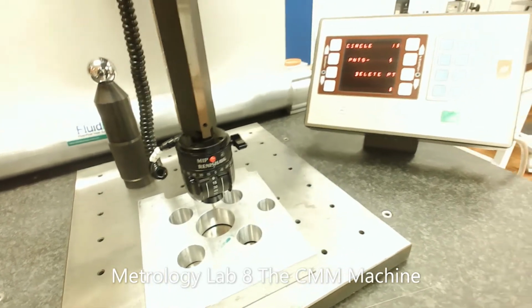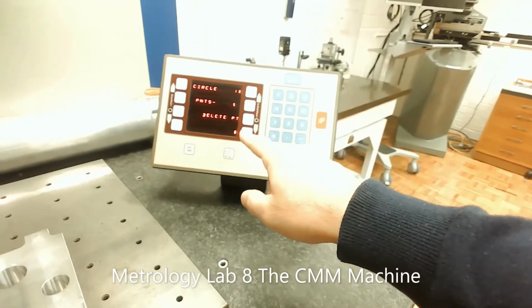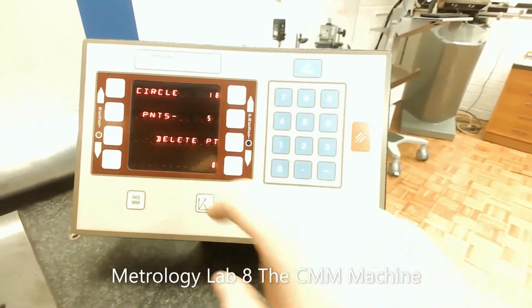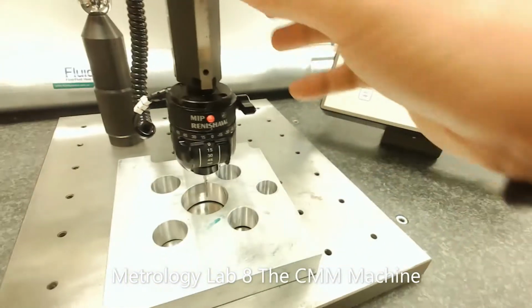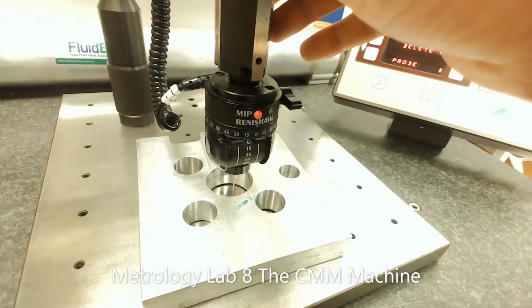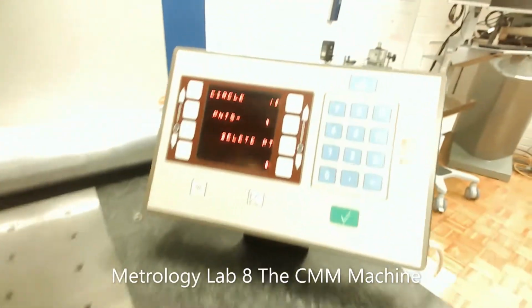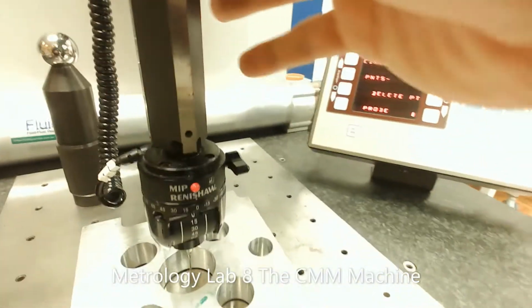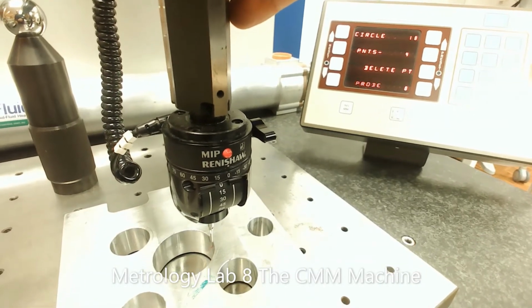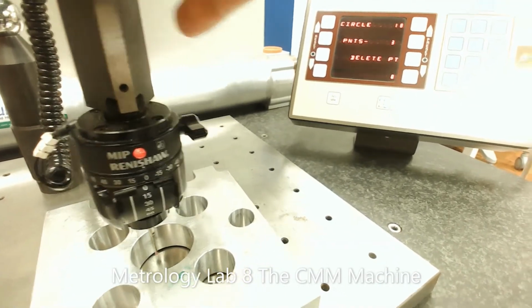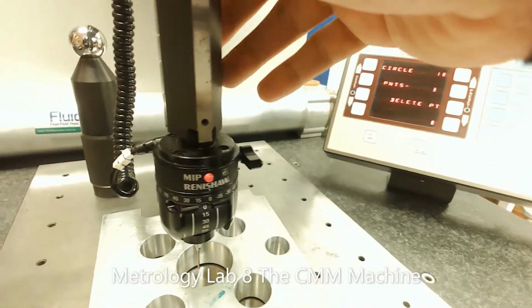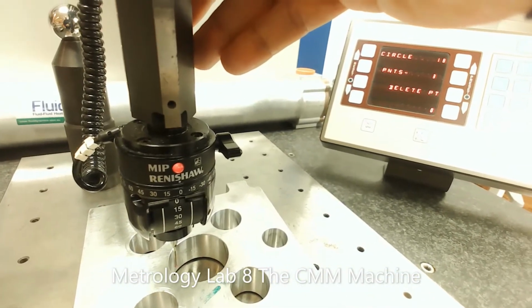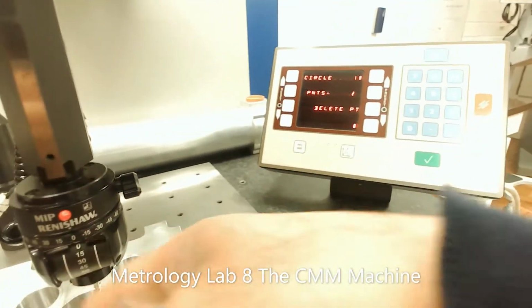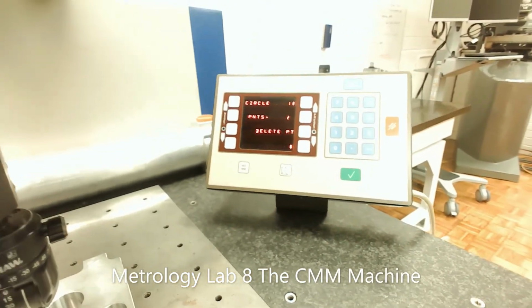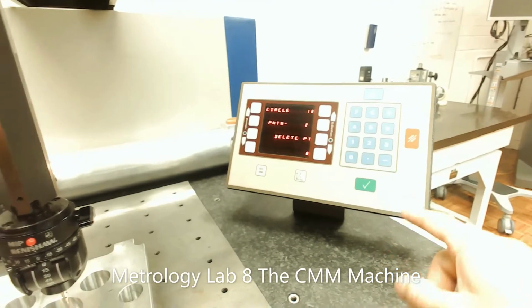I got first touch. Now I'm going to have another 5 readings to be measured. Say measure. I'm going to move it to the other side. For measure, I need to distribute the location of the point of the measurement to a different location in the circle. So what's happening here is that the device is going to do the circle by approximating the diameters and then check the average and give it to you right here.